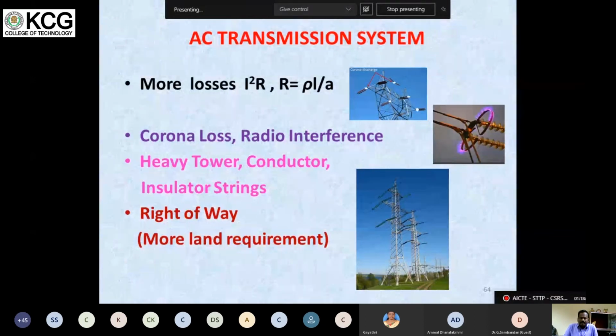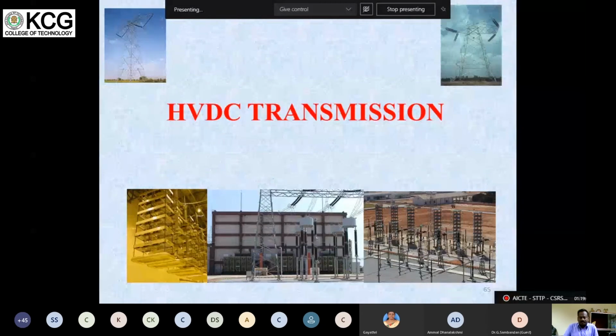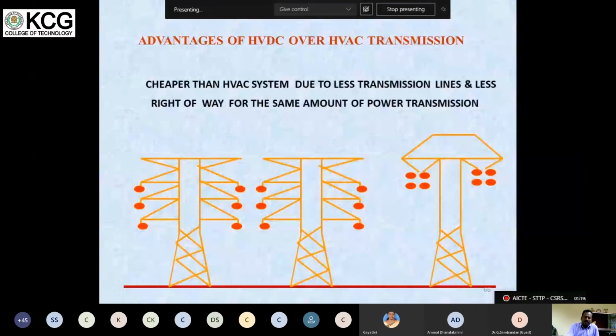Then the AC system has some other problems also: corona losses and radio interference. The AC system also needs heavy towers, conductors and insulator strings, and more land. So we cannot replace the AC system, but to supplement the power transfer in the grid system, we go for the HVDC transmission system also. In the HVDC transmission system the loss is lesser than in the HVAC system. Take the first two towers of 400 kV: there are 4 circuits, double circuit towers, 2 towers. Let us say the power transfer is 2000 megawatt, but this 2000 megawatt can be transferred with a single tower HVDC system. That is the advantage of the HVDC system.